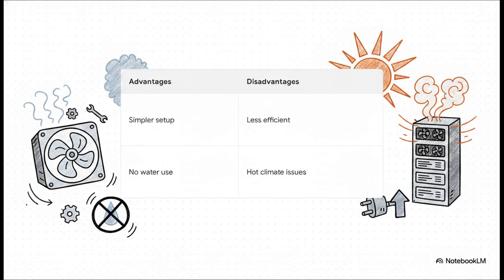On the plus side, air cooling is so much simpler. You don't need elaborate cooling towers or condenser water pumps. And the biggest win? They use little to no water for heat rejection. That means you completely avoid the strict water treatment requirements that come with other systems. This makes air cooling a huge win for smaller edge facilities, quick retrofits, or places experiencing droughts where water is heavily regulated. But, there's always a catch.